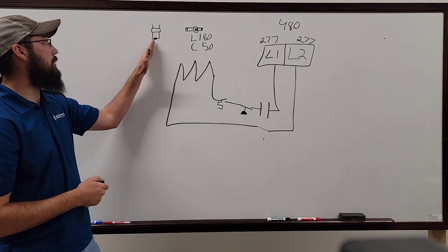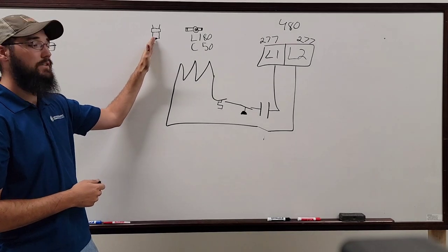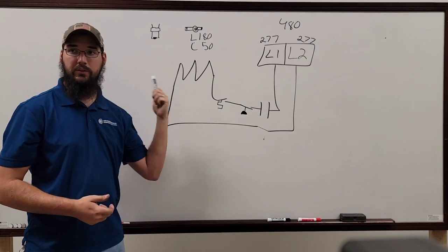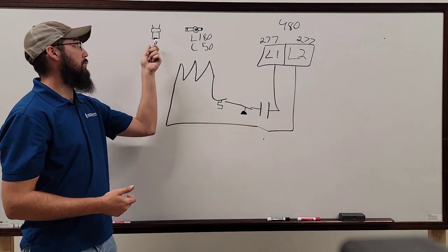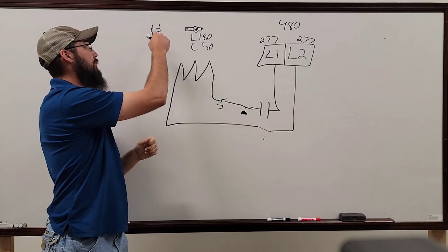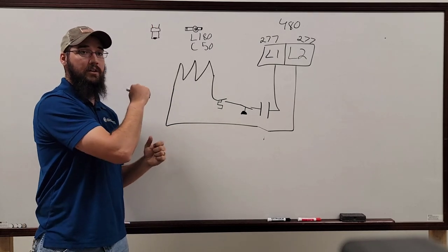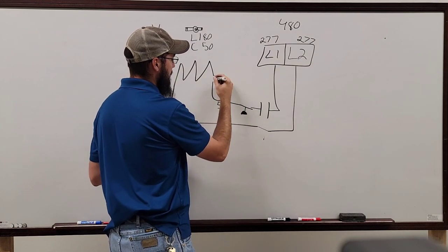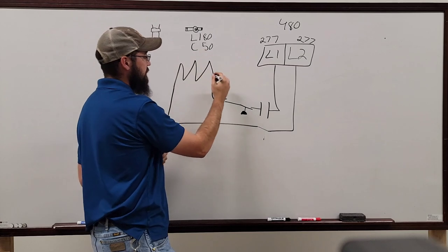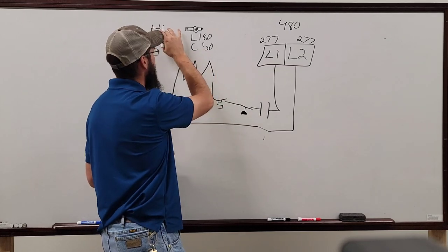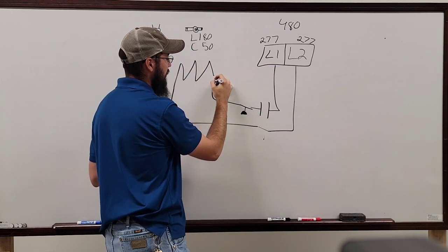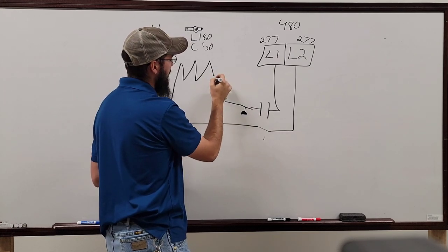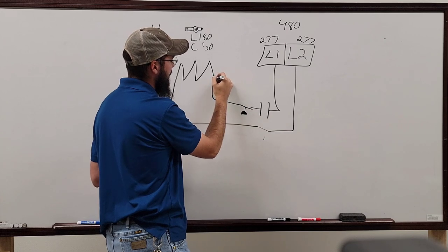Like I said, these do still exist. I don't know how much you will see them, but if you ever do, at least you know what it is. It's a fusible link. The really, really old school ones were before they even started putting them in the ceramic. They would literally wire in line. And these are in line, by the way. These are a load duty limit. They could be pilot duty, but most of the time they weren't.